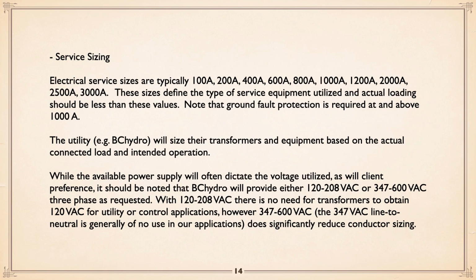Very cool. Service sizing. The service sizes typically provided by the utility are 100 amp, 200 amp, 400, 600, 800, 1,000, 1,200, 2,000, 2,500, 3,000. These sizes define the type of service equipment utilized, and the actual loading should be less than these values. Note that ground fault protection is required at and above 1,000 amp. That's a story unto itself. But those are basically the standard services.